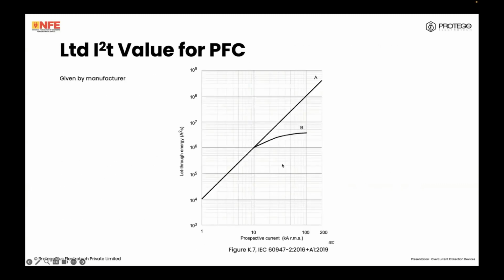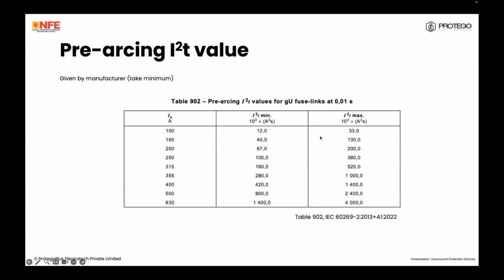So once again, we'll find out the current limited I square T value. You can see now why current limiting is becoming so important, especially for selectivity. You get this value corresponding to the relevant prospective current. This we know, we can calculate, we can even measure. This is the limited let-through energy. And what is the pre-arcing let-through energy for the fuse? This is given by the manufacturer and the standards.